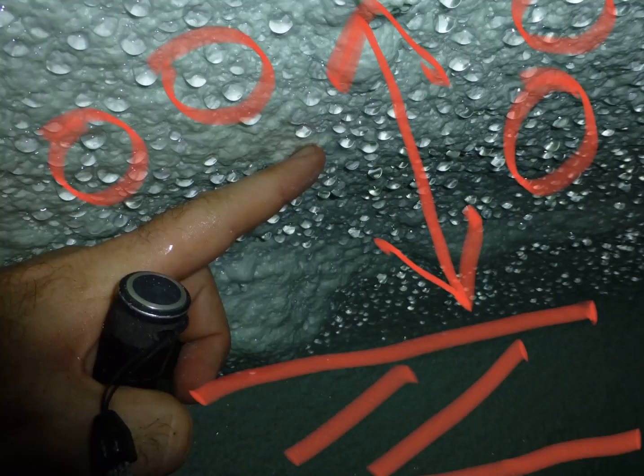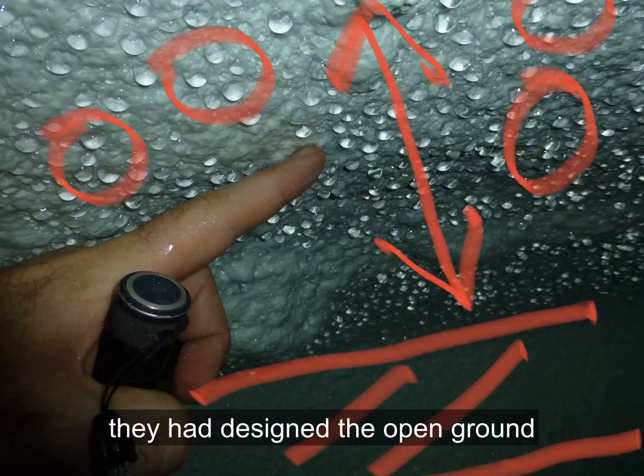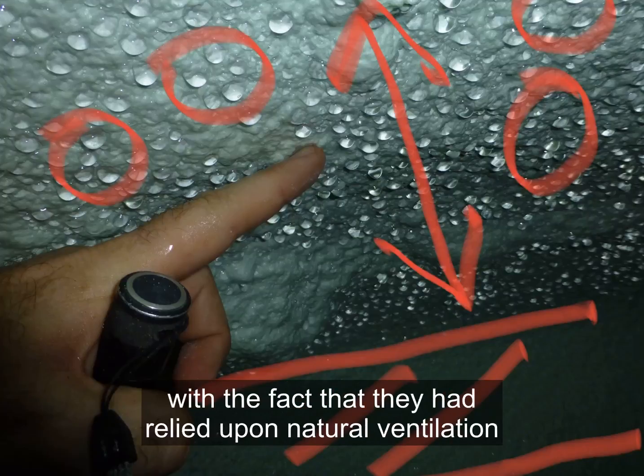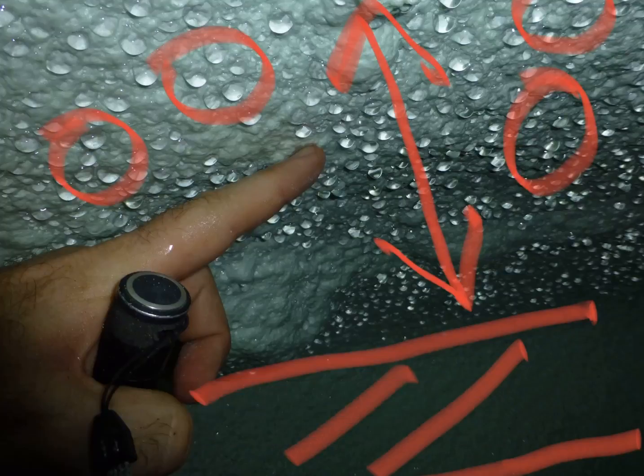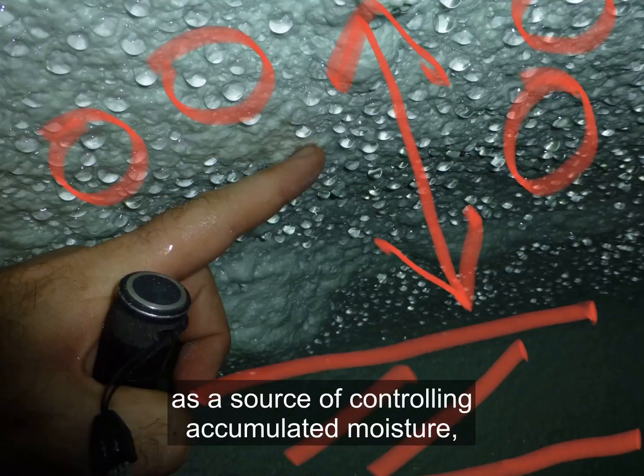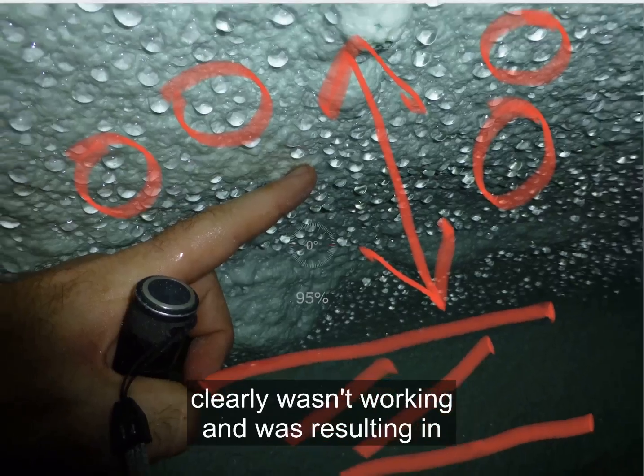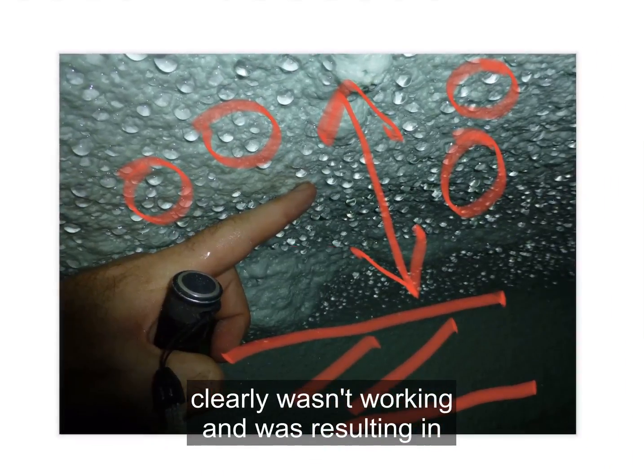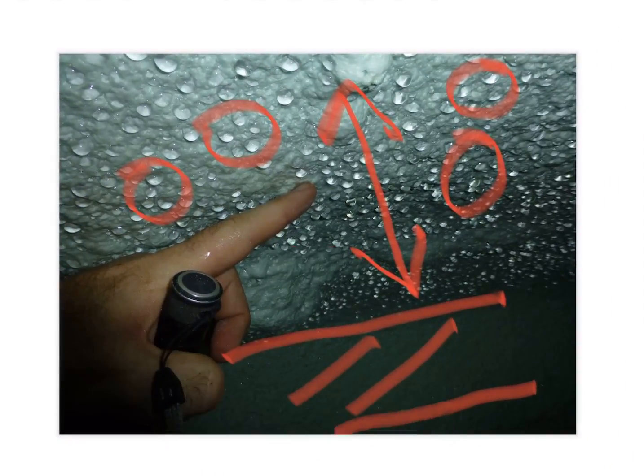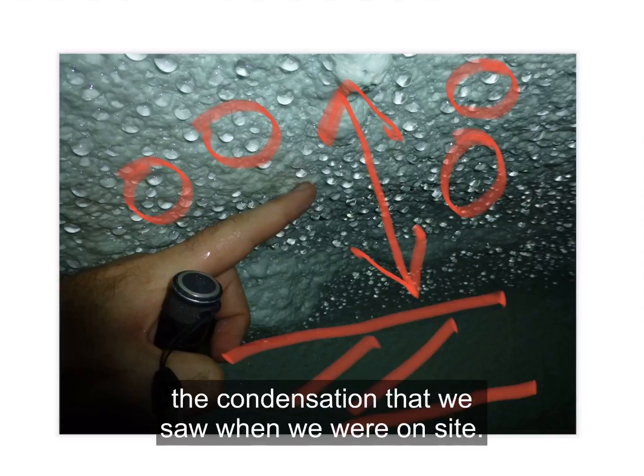And so the combination of the way they had designed the open ground, with the fact that they had relied upon natural ventilation as a source of controlling accumulated moisture, clearly wasn't working and was resulting in the condensation that we saw when we were on site.